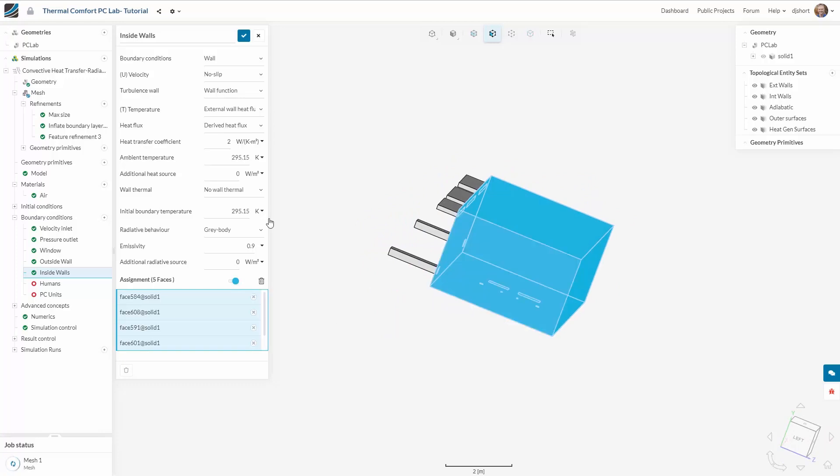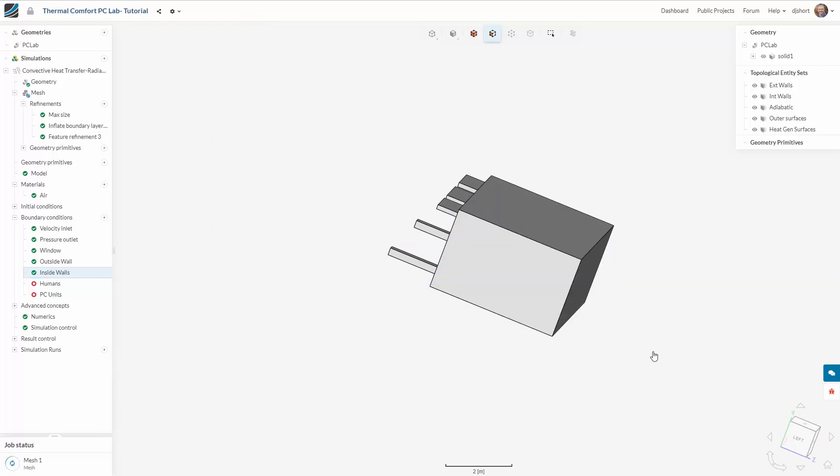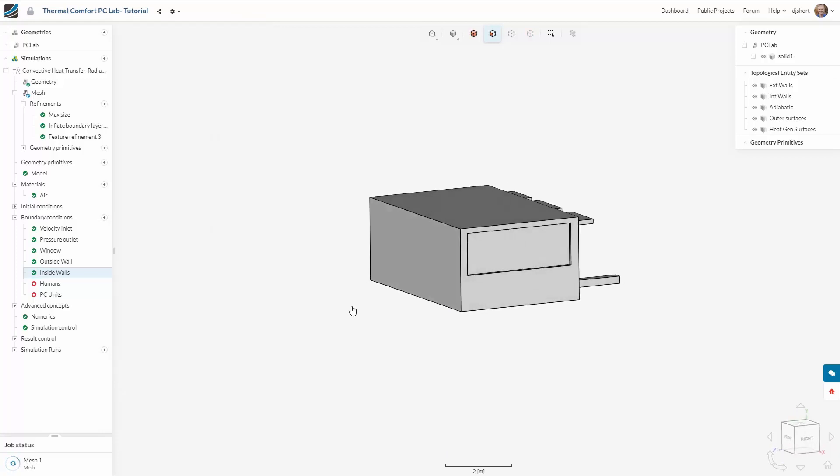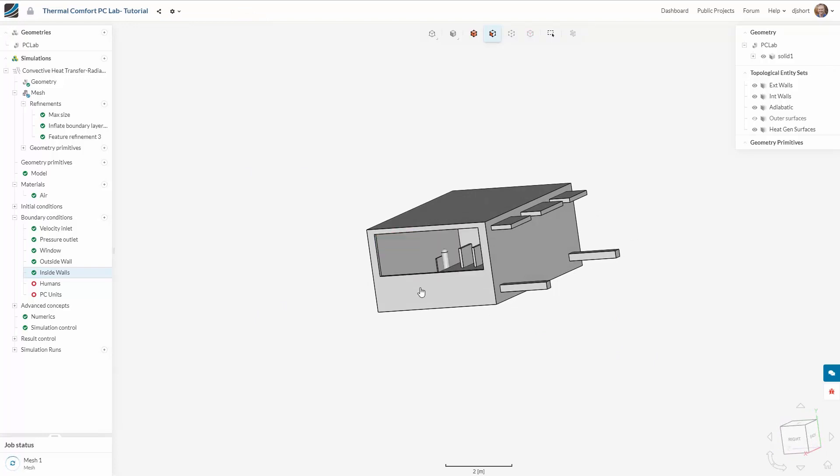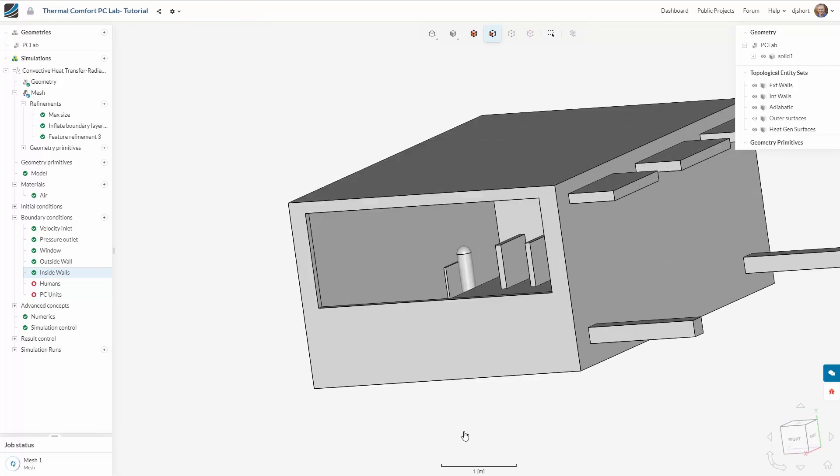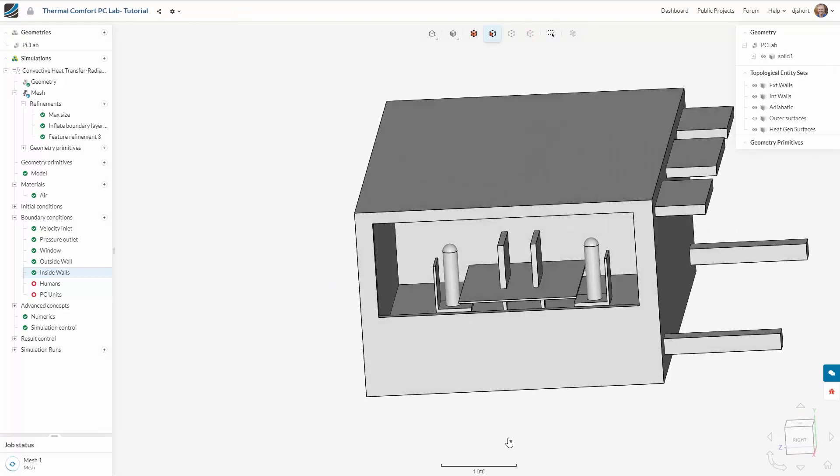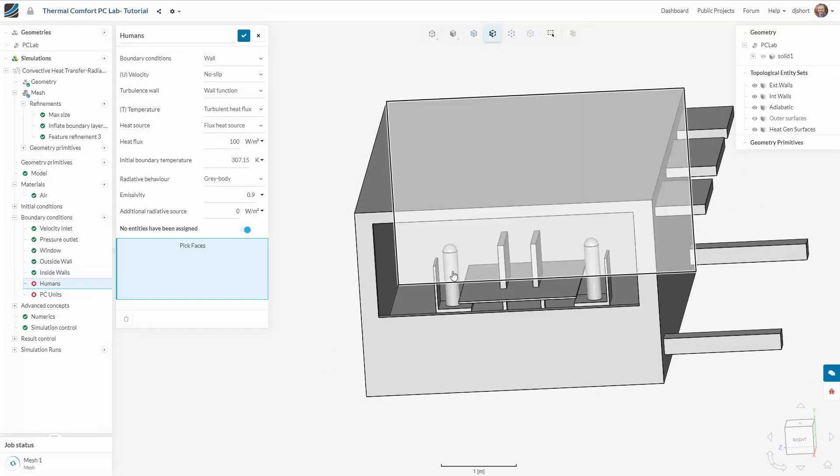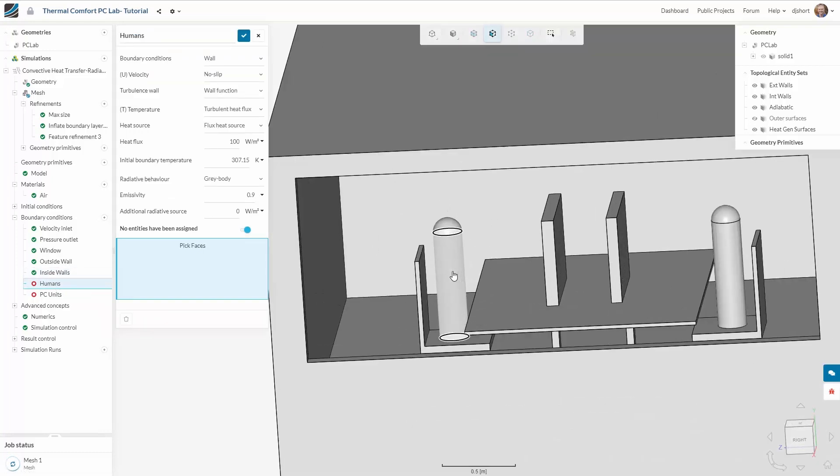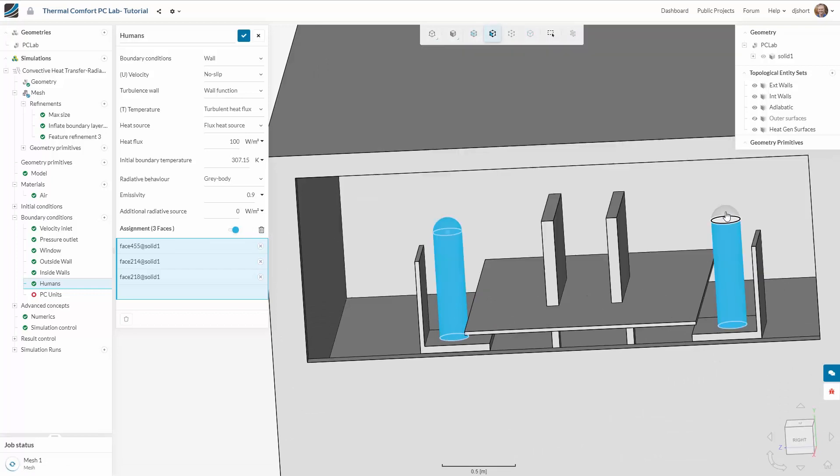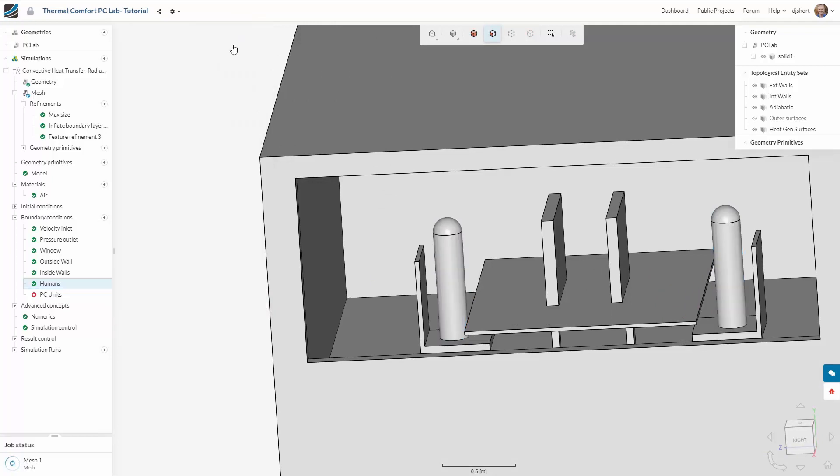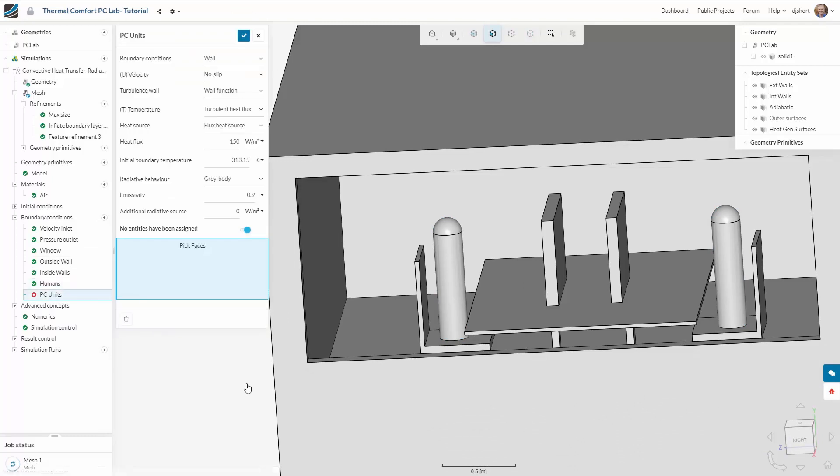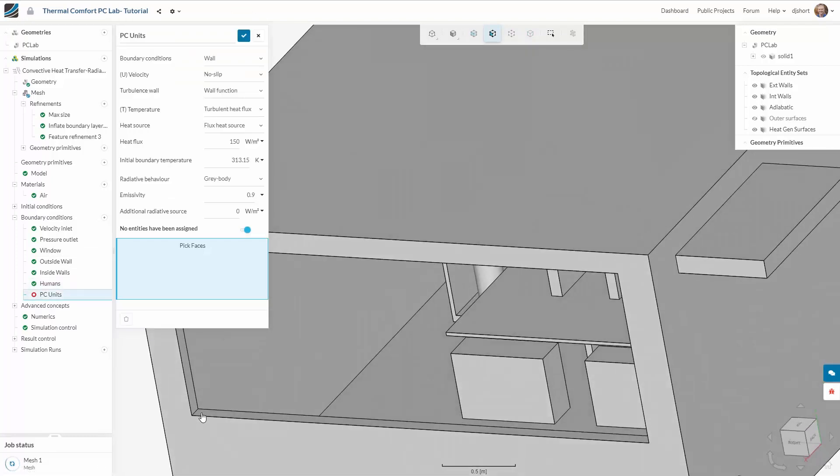To input the heat generation into the system I'm going to use wall conditions applied to the humans and to the PC units. I use a turbulent heat flux on the humans and give the heat flux value of 100 watts per meter squared equivalent to the metabolic rate of the humans. I repeat this process for the PC units adding a slightly higher heat flux.